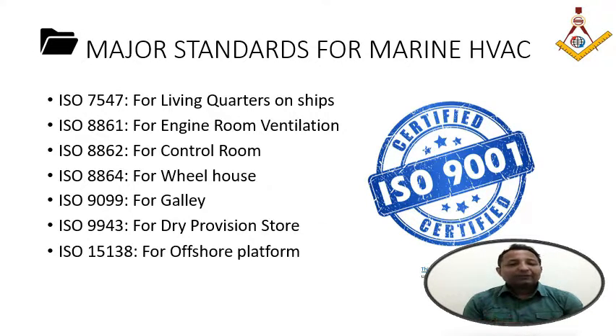Then ISO 9099 is for the galley - the kitchen. This is a very important chapter which I will cover in subsequent lectures. For the galley, the supply and exhaust system is designed based on heat dissipation from the galley equipment, which works on a cycle since it's not operating 24/7. There are shifts - morning breakfast, afternoon, and evening - only in these three shifts the galley operates, with heat dissipation from fryers and burners. We need to consider all this while designing the galley, and if values aren't given, the standard provides certain values to follow.